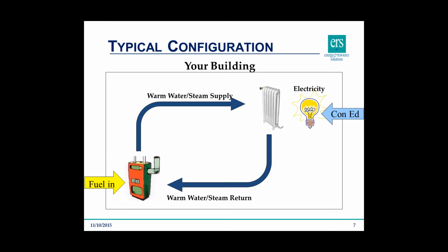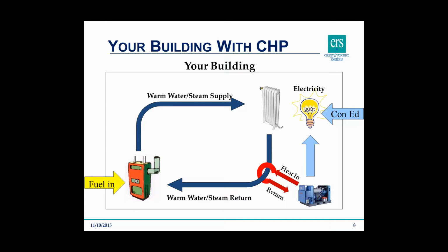Now a CHP system would slot right alongside those existing systems. One of the nice parts of CHP installations is that they don't require significant rework to any of your electrical or thermal infrastructure in your facility. It would slot right alongside, use natural gas, go into this engine, produce electricity to supplement electricity produced off the grid, and at the same time add some heat into the hot water and space heating loop on this building.